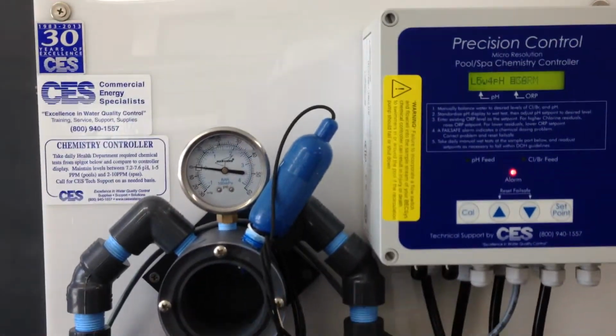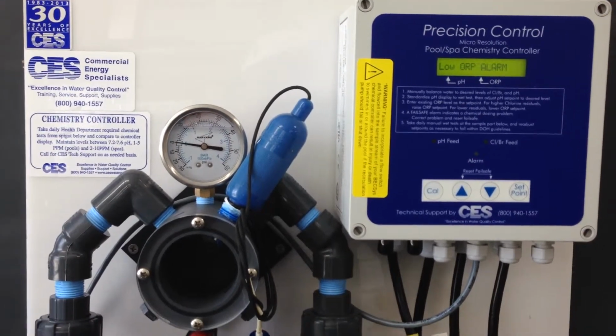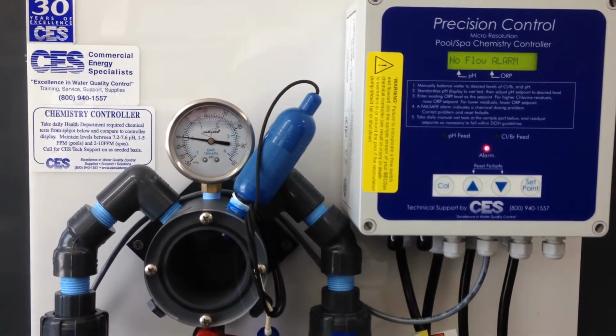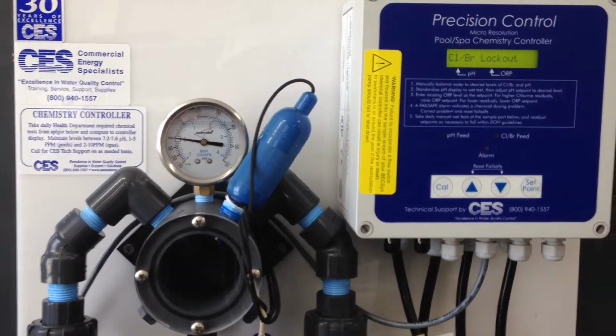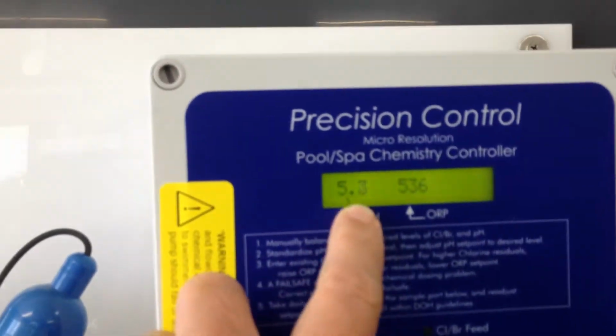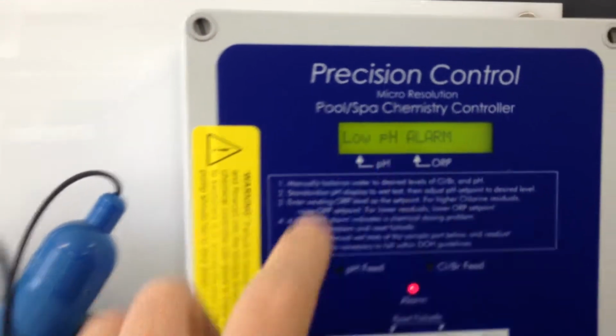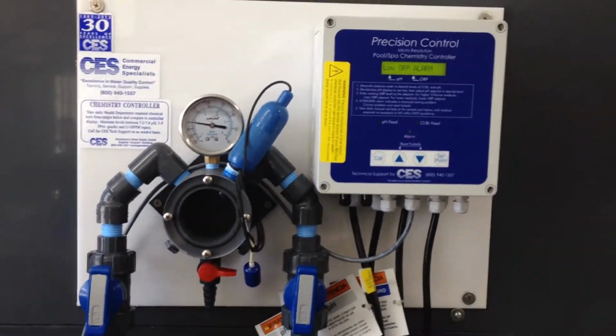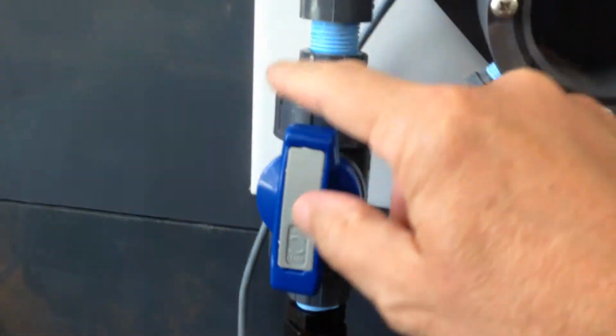So that's more advanced, but if you ever see a lockout, what you have to do is correct the condition, and it'll tell you what the conditions are here. So that's in a nutshell. I figure the toughest part for you guys is to make sure that this line is about the same size as what you had before, and that you tie it in on the pressure side coming in through the left, and then take this back either to the open tank or into the suction side of the pump.